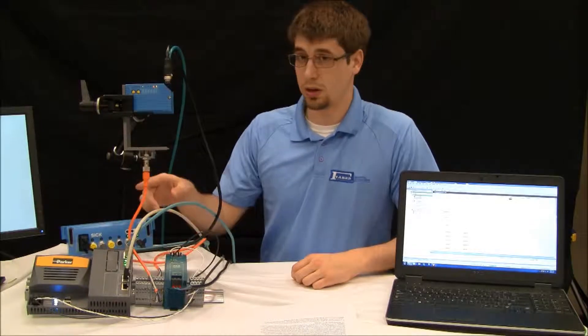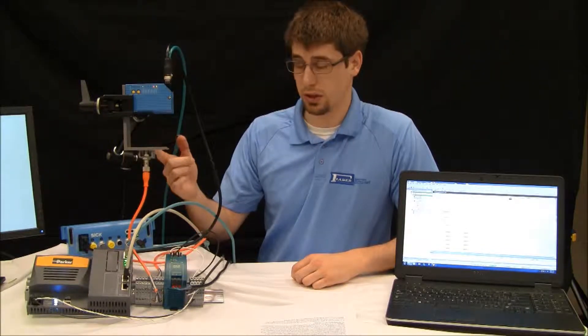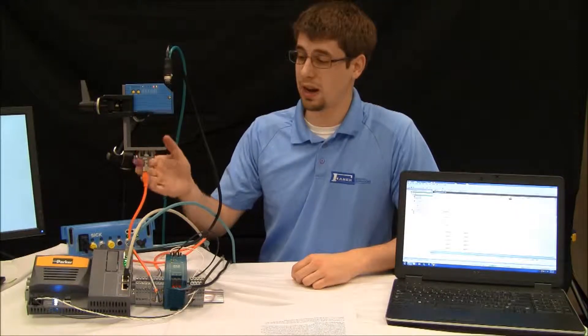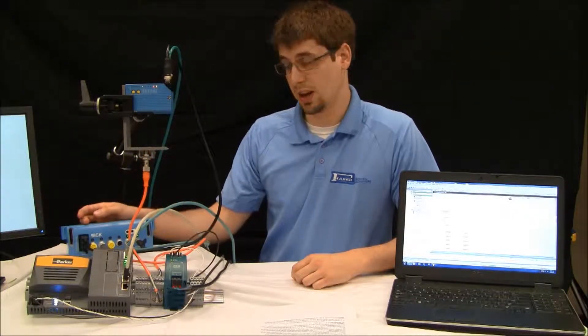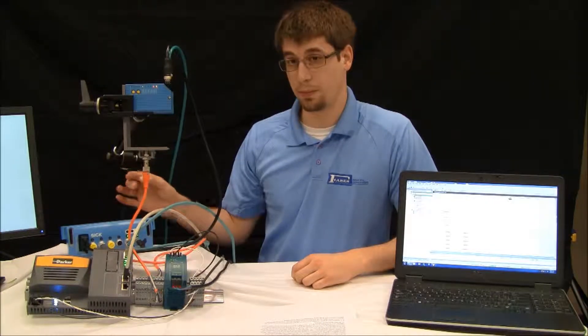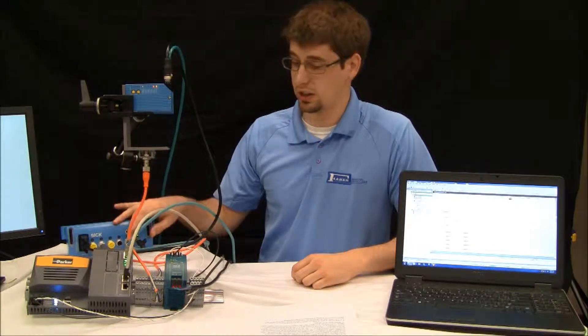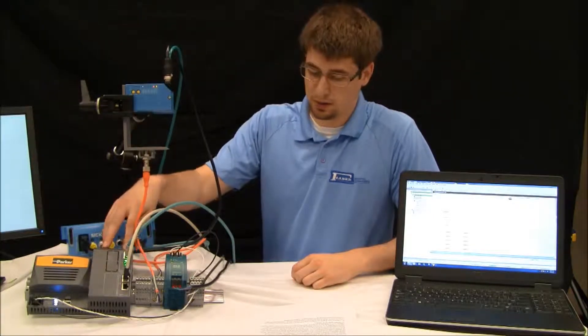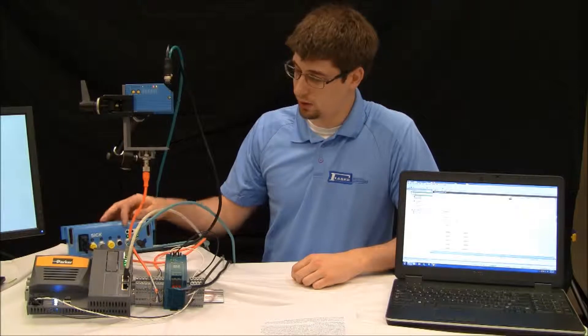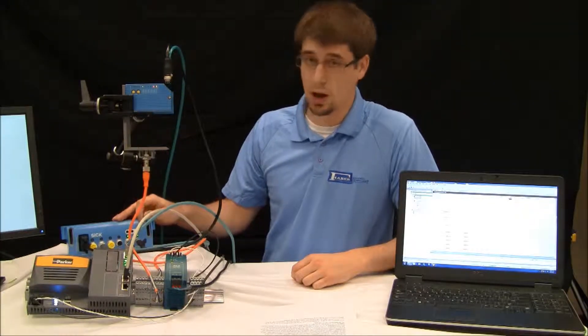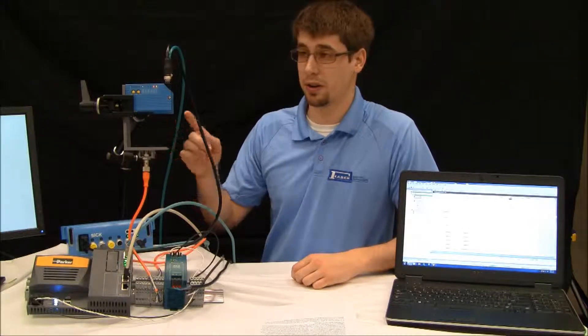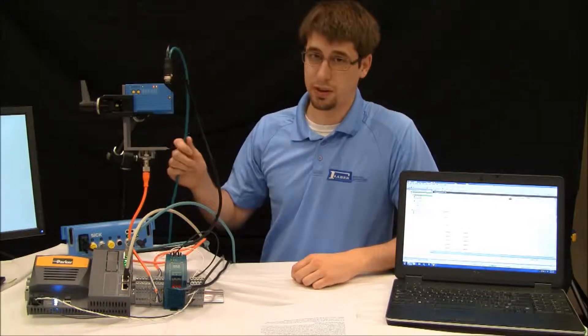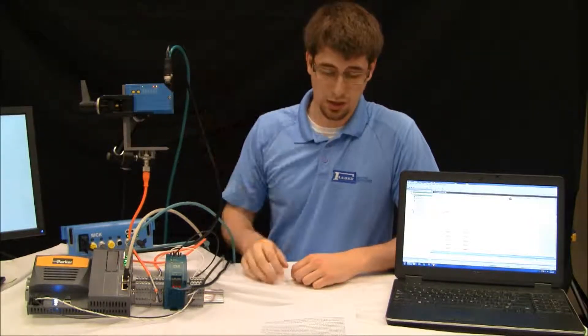We will also be using a magnetic proximity sensor to trigger the barcode scanner. Both the barcode scanner and the magnetic proximity sensor will need to be wired into the EtherCAT module using the proper cables. And then the field bus module will in turn need to be wired into connector X1 on the PAC. Since we'll be using the EtherCAT network, we're going to be leaving the rotary switches on the top of the field bus module all set to zero.